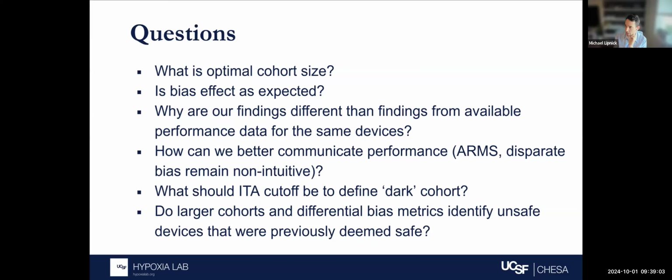Yeah, thanks for the question. So for some of the devices we are, in particular our two reference devices. We have two other reference devices we don't yet have large enough cohorts for, which are a Philips device and a Nihon Kohden device. But for the Masimo Rad97 and the PM1000N, we are testing both of those in multiple probes, including the wrap style disposable probes as you're describing, as well as reflectance forehead, and then also for some of the multi-wavelength, greater than 2 wavelength probe types. So we hope to be able to share that as well.